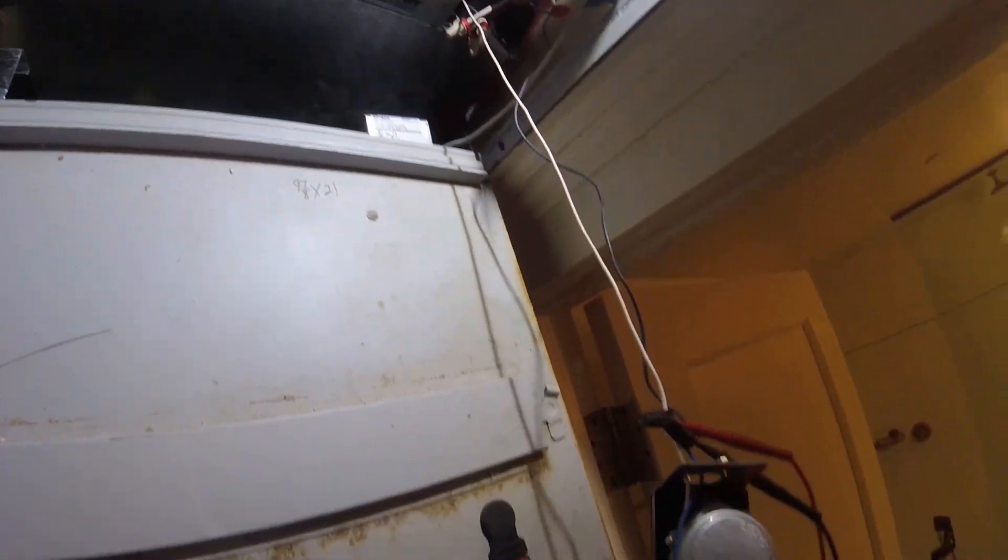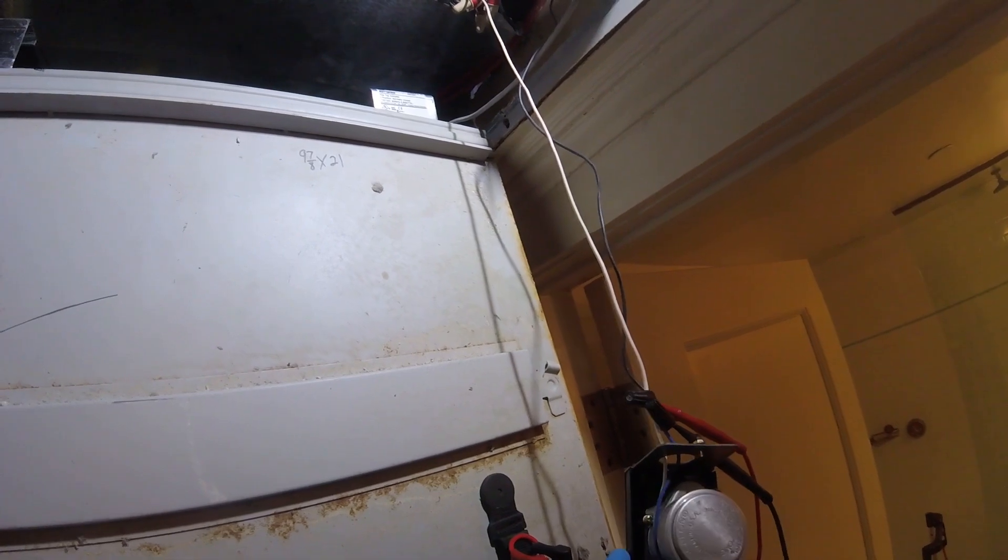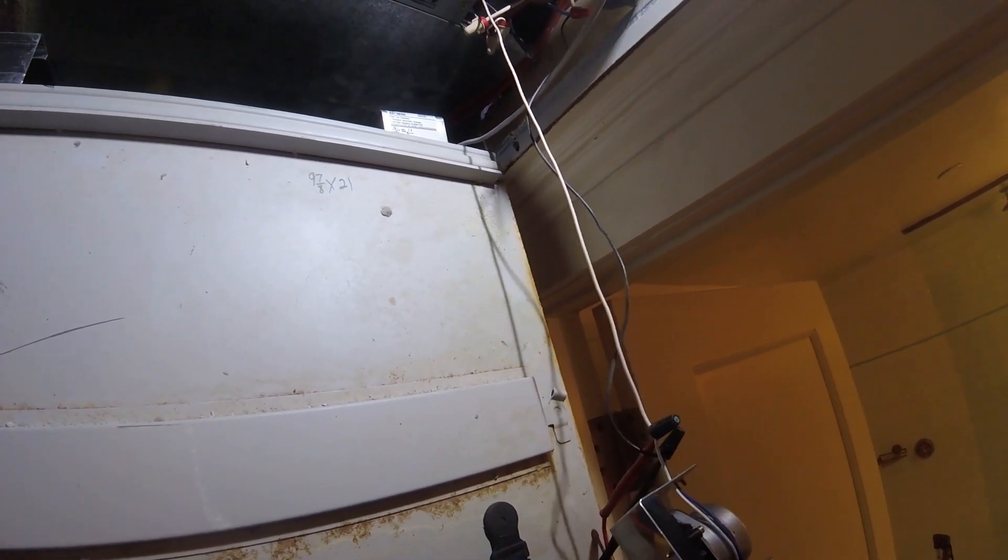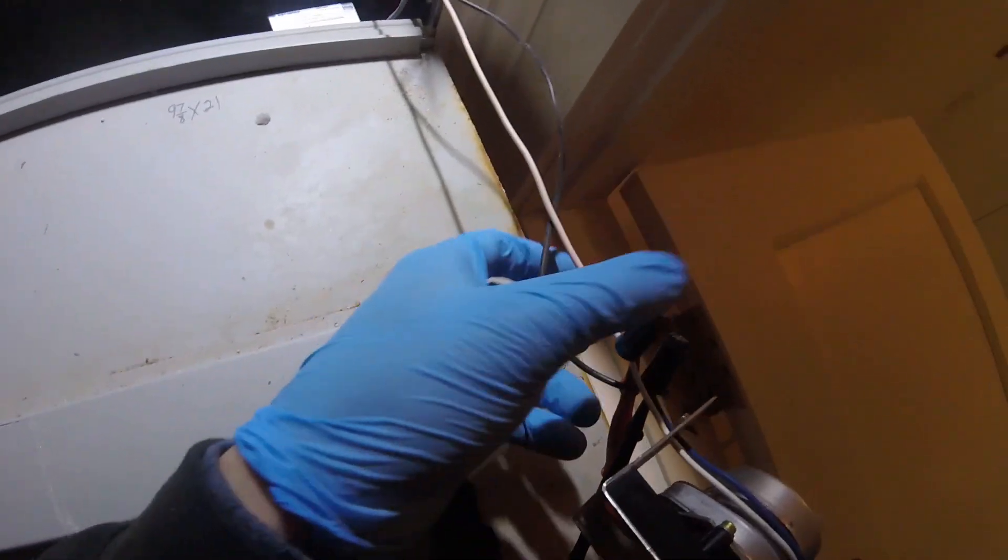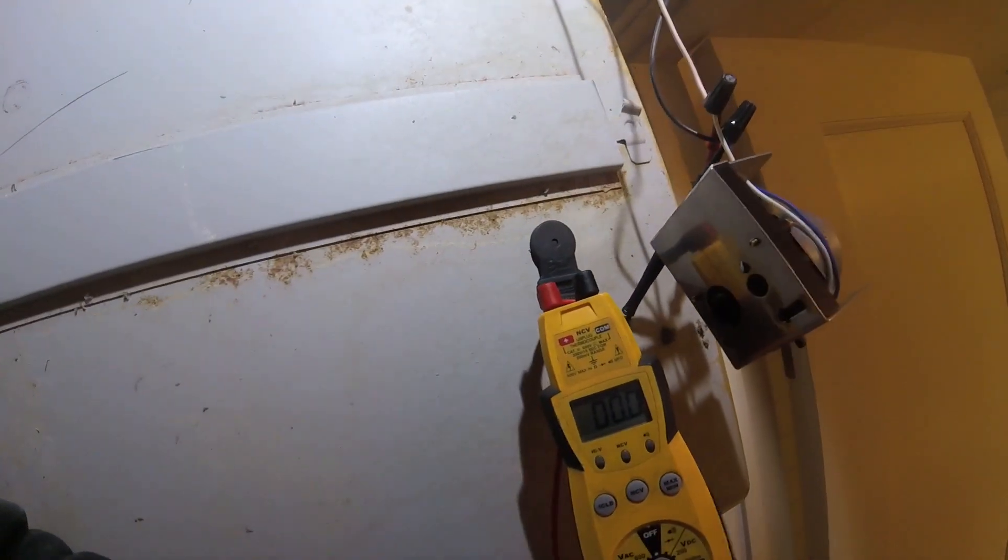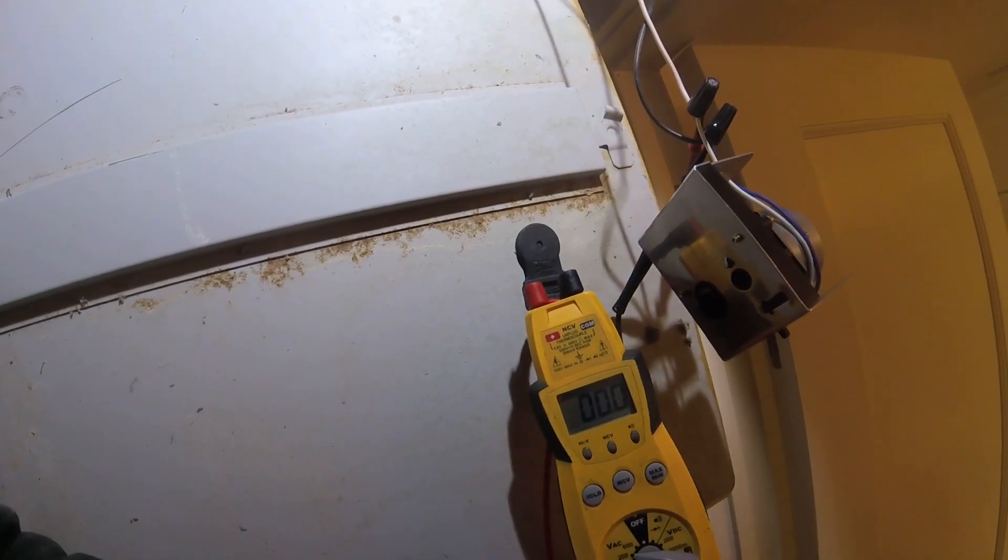When we open this cover I found the actuator just hanging there so they just had it bypassed. So the valve is, the water is always running. So I got my meter between the two terminals. We're in heat mode. I have it set to cooling and we have no voltage so that's good.